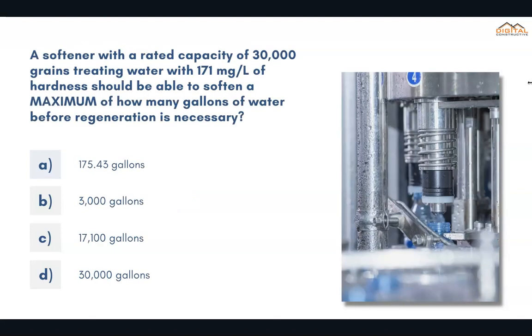A softener with a rated capacity of 30,000 grains treating water with 171 milligrams per liter of hardness should be able to soften a maximum of how many gallons of water before regeneration is necessary? The correct answer is B, 3,000 gallons.